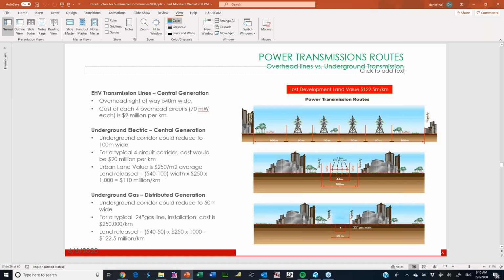So we did a land use study for the various alternatives. First, extreme high voltage transmission lines with central generation. The overhead right-of-way required for these very high transmission towers into the city was approximately 540 meters wide. The cost of each of the 4 overhead circuits, 70 megawatts each, was $2 million per kilometer. The development value of the land was $122.5 million per kilometer for this alternative.